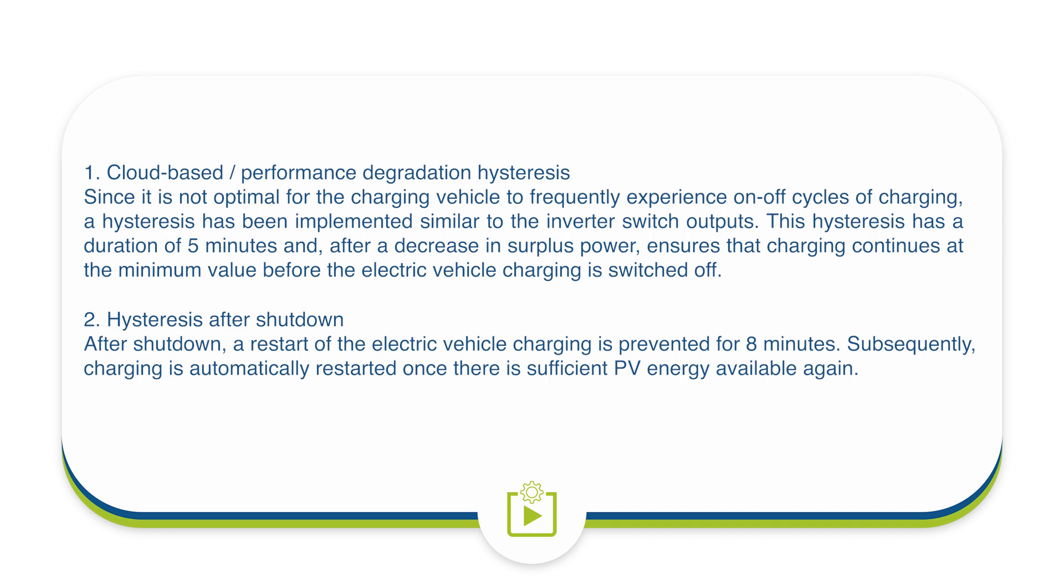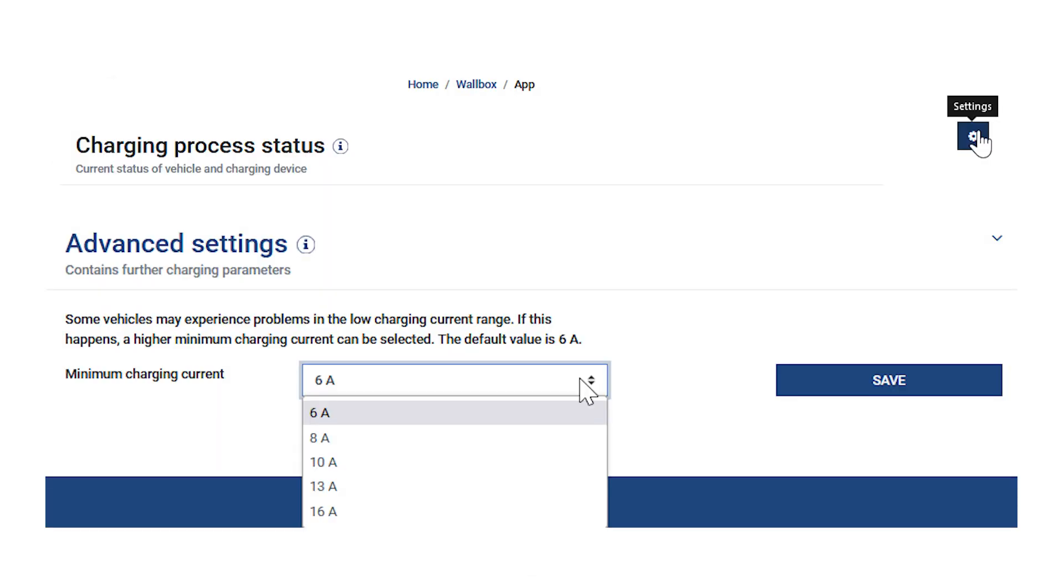Secondly, hysteresis after shutdown. After shutdown, a restart of the electric vehicle charging is prevented for 8 minutes. Subsequently, charging is automatically restarted once there is sufficient PV energy available again.